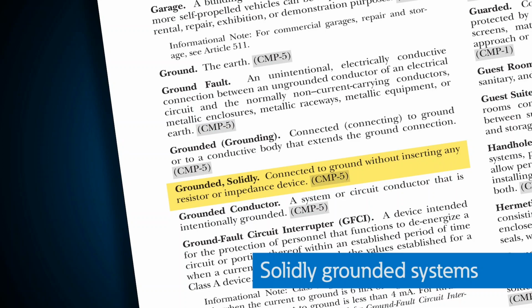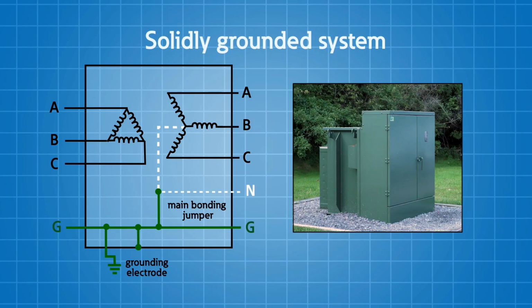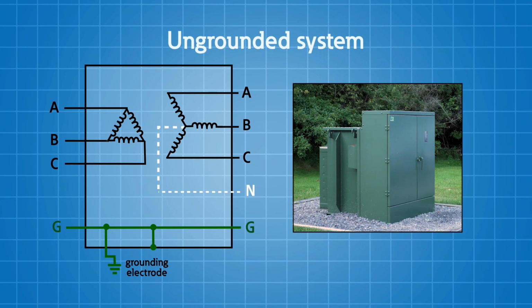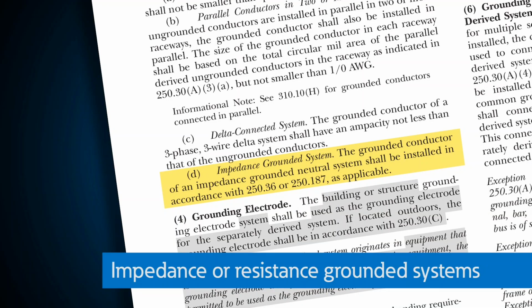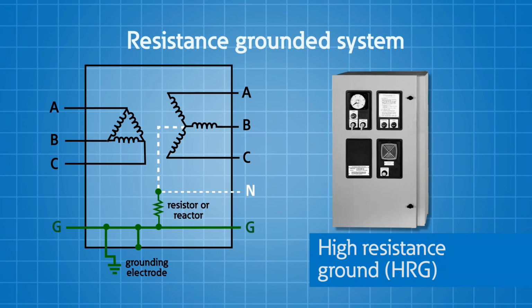All right, so everything that we've talked about so far has been about grounding and bonding of components and electrical systems. We're establishing that connection at the service or at our separately derived system between the grounded conductor and our equipment bonding and ground and earth. Now we're going to talk about system grounding, and we're going to hit solidly grounded systems versus resistance or impedance grounded systems. Solidly grounded, when we use that terminology, means we have a solid connection to the earth at some point in the power distribution system. There's no resistor or impedance inserted in that connection point. Ungrounded systems are just that. There's no connection to ground or a conductive body that extends that ground connection. We're insulated from ground. Your impedance or resistive grounded systems are systems that are connected to the ground, to the earth, through an impedance.